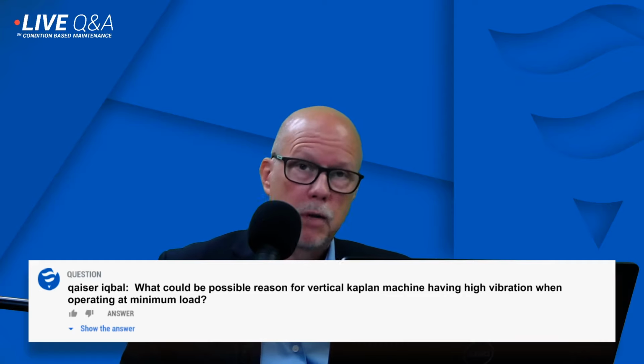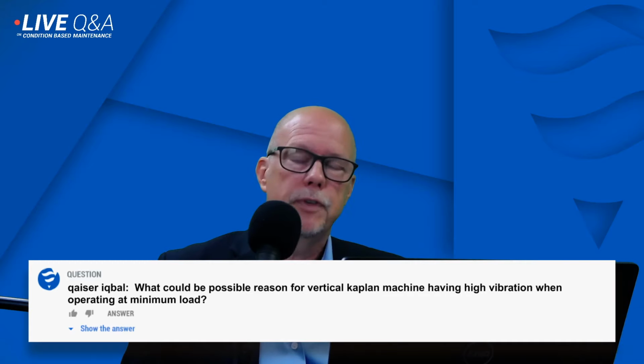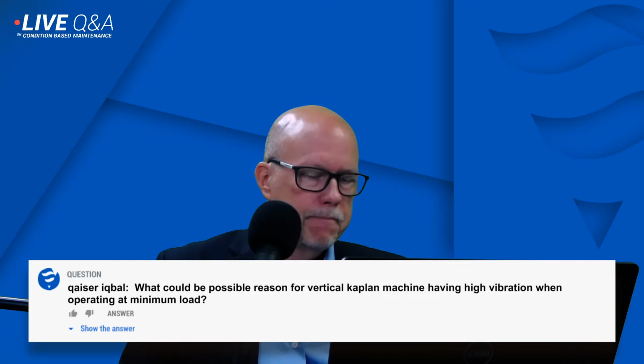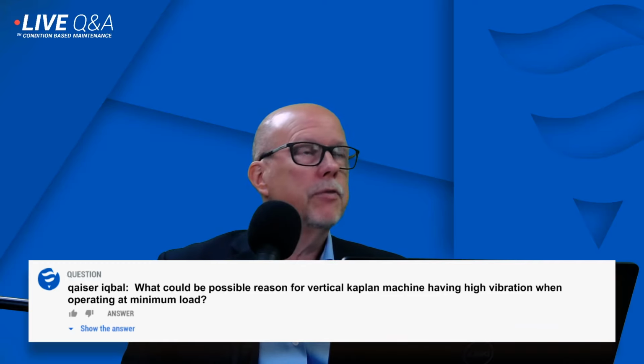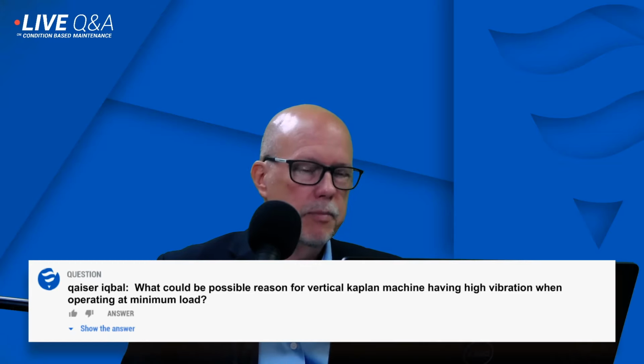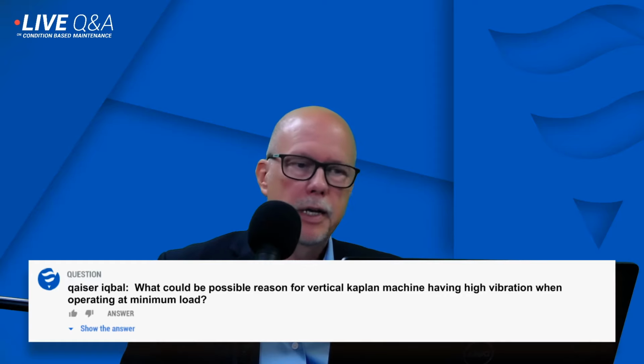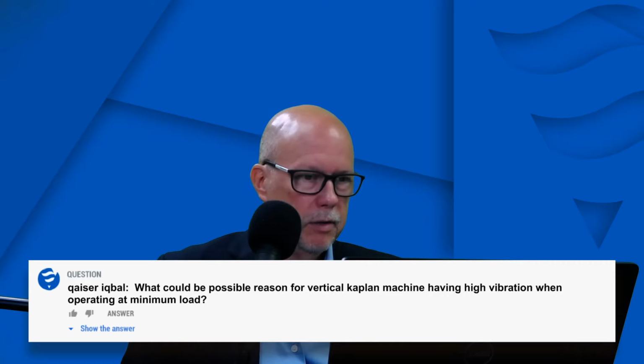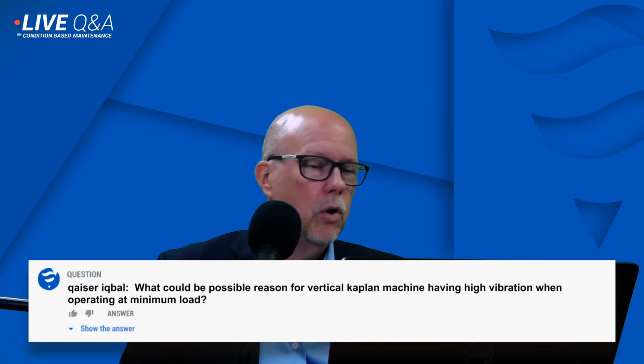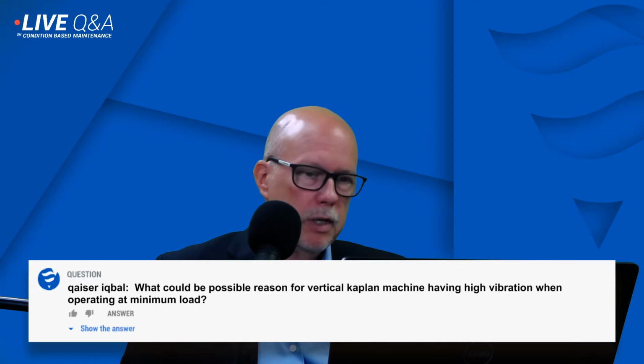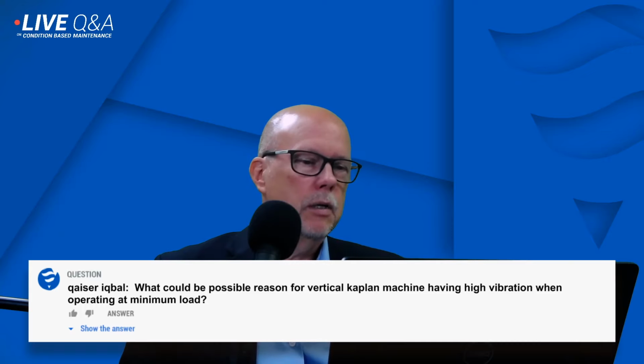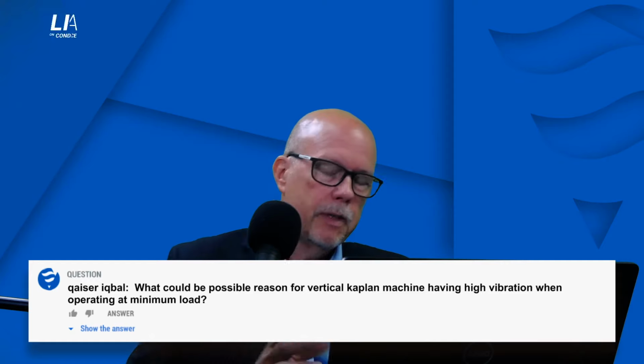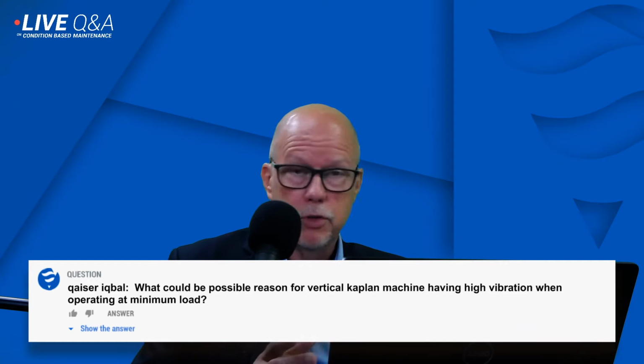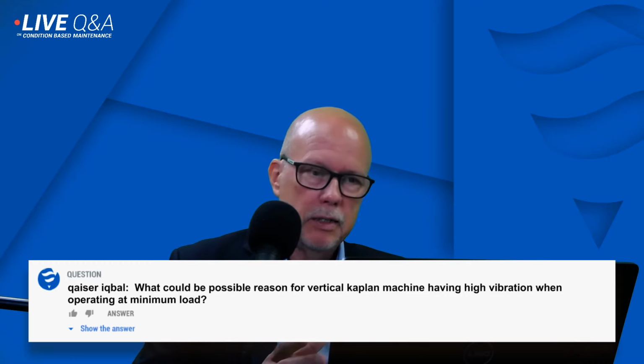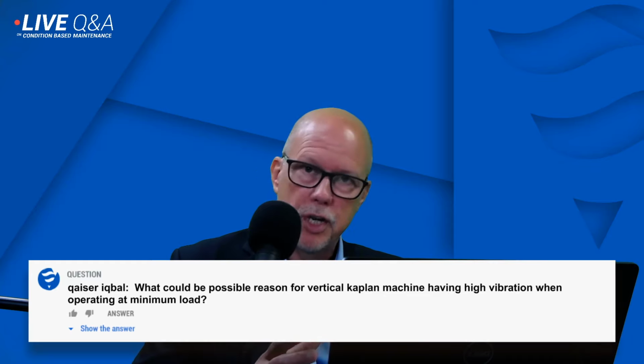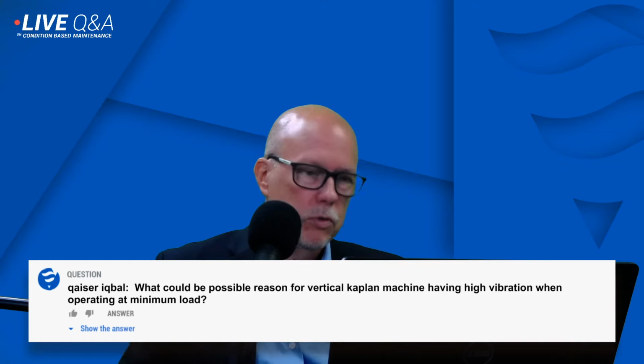Now, if you have a unit that has this problem at all loads, that means you need to fix the bearing. If the vibration is immediately after synchronizing, so that you're synchronized to the grid but you're not actually producing any power, that could be an indication of either an out of round stator, or it could be also a combination of rotor and stator. And if you increase the load and it settles, which is one of the reasons why we look at the stator expansion as well, some stators, when they expand, actually improve, which is good news. So that when you operate at higher loads, the heat will in fact fix the shape of the stator, and the unit will quiet down, the vibration will go down.